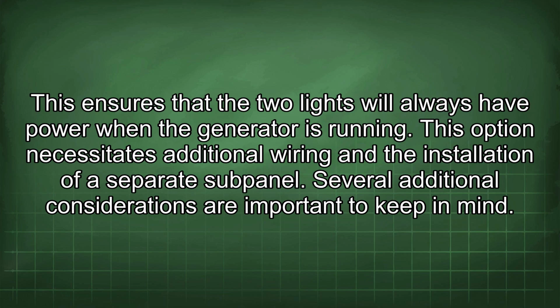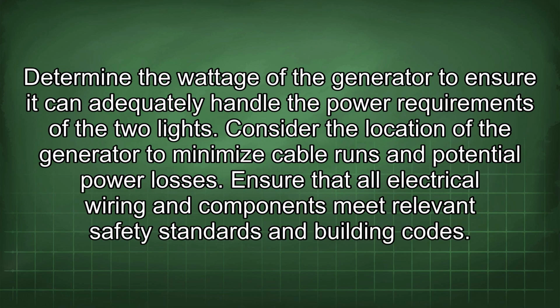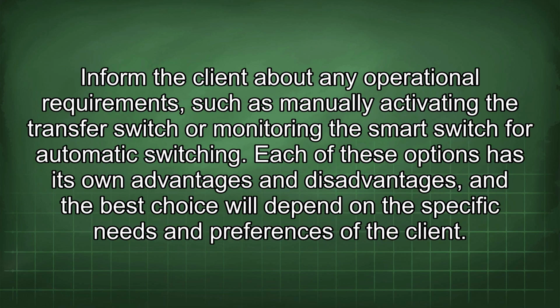Several additional considerations are important to keep in mind. Determine the wattage of the generator to ensure it can adequately handle the power requirements of the two lights. Consider the location of the generator to minimize cable runs and potential power losses. Ensure that all electrical wiring and components meet relevant safety standards and building codes. Inform the client about any operational requirements such as manually activating the transfer switch or monitoring the smart switch for automatic switching.